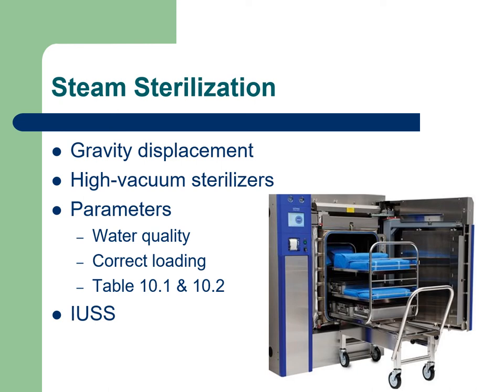Also important is making sure we load the sterilizer correctly. This image is an example of a large capacity steam sterilizer, huge sterilizers found in the sterile processing department. We want to make sure we don't overload them, that we place linen packs on their sides. Packs and instrument trays should be placed so they do not touch. You don't want to jam pack the cart with instruments, because steam needs to be able to circulate in and around those packages and trays.